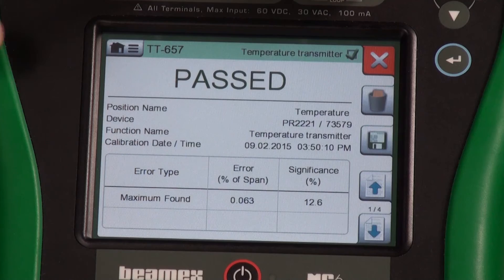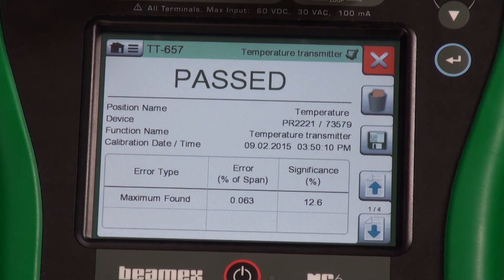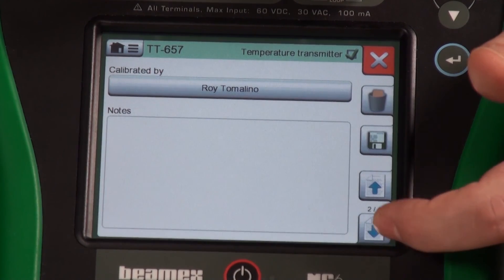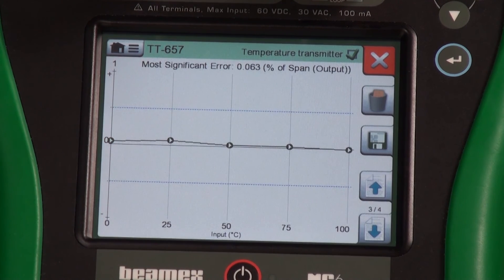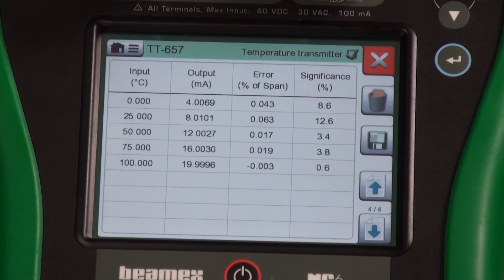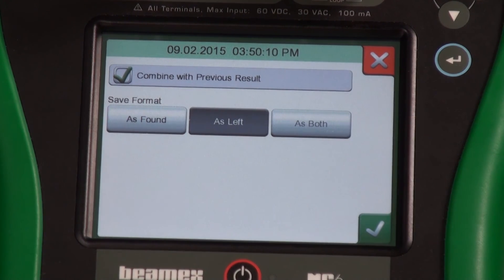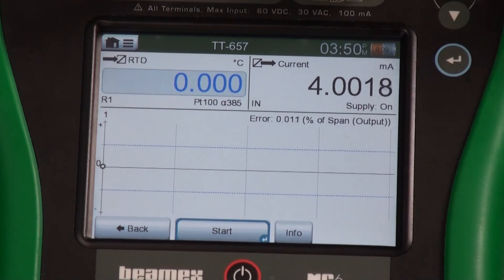It's quite a bit flatter than our previous. As a calibration technician, I've done my duty in performing an as-found, I saw a failure, I went in and trimmed that error out, and have done an as-left — leaving it in a passing condition. Before we had red failed, and now we have a green passed. We can see our error: now we have only 0.063 percent of span error. I can go down to add notes, see visually what the graph looked like, and see all my raw data. Let's save this — as-left is selected, we want to save this as-left, and I'll hit my check mark. Now I am complete. We've successfully done an as-found, a trim, and a passing as-left test result.